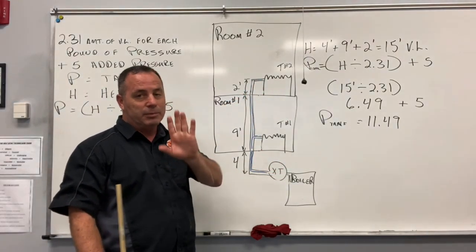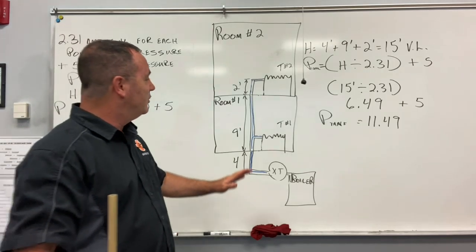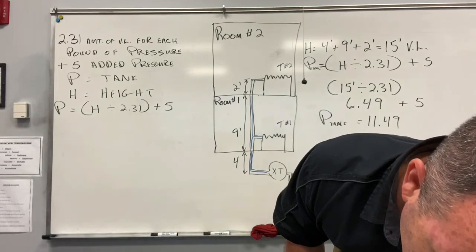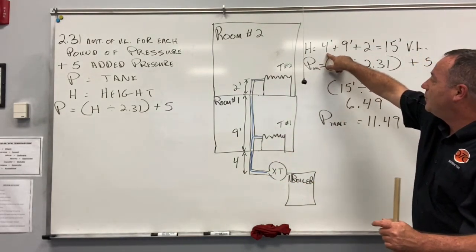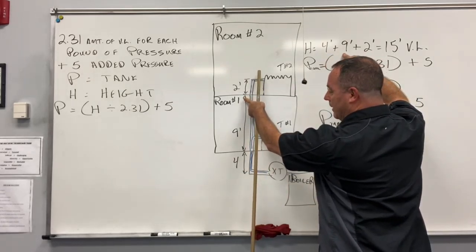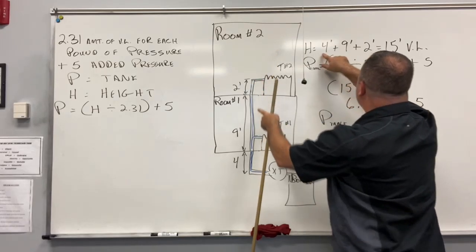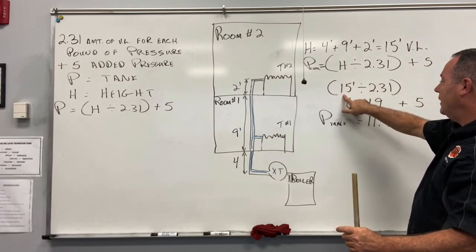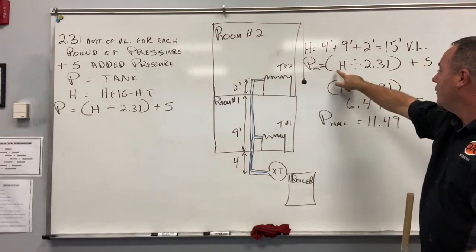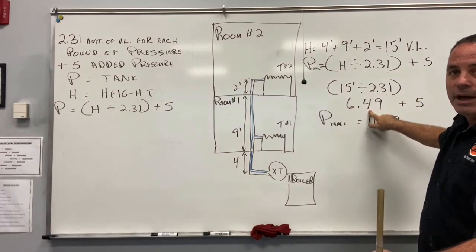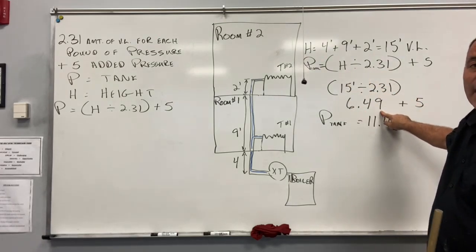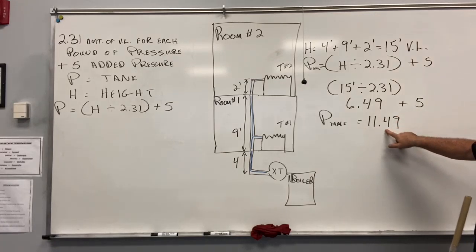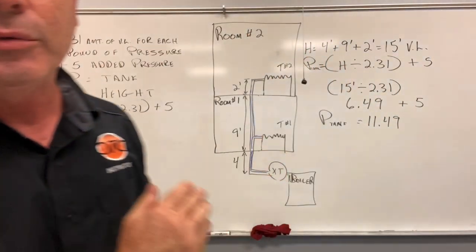Working through the math from page 975: the total height H is 4 + 9 + 2 = 15 feet of vertical lift. Using the formula: 15 ÷ 2.31 = 6.49, then 6.49 + 5 = 11.49 PSI. So the required expansion tank pressure is 11.49 PSI, which is what the book calculates.